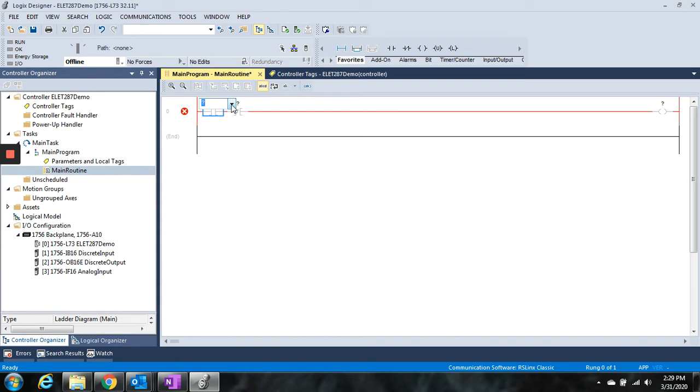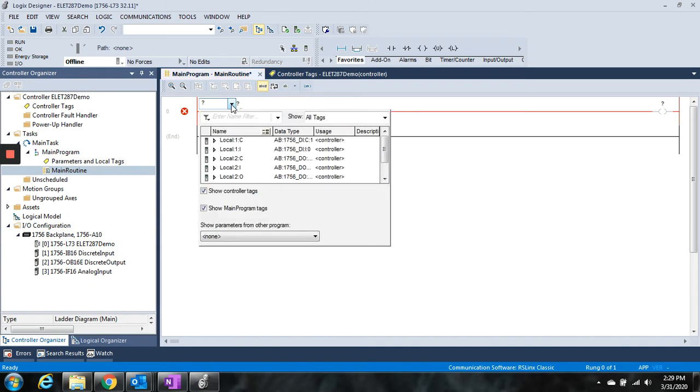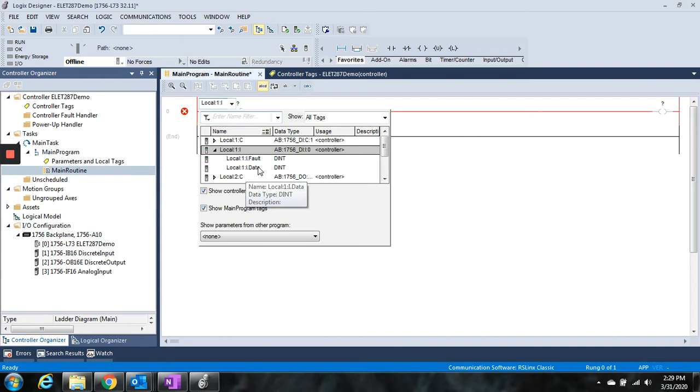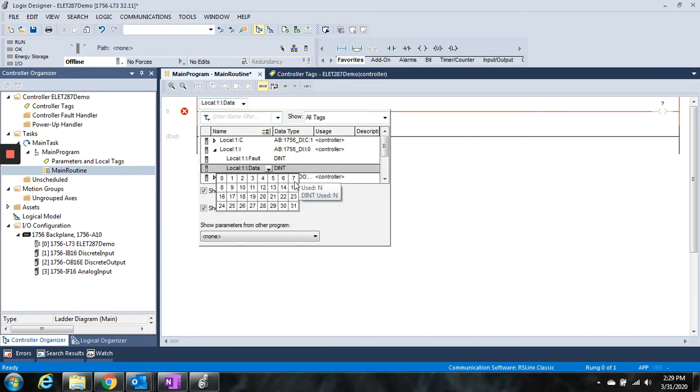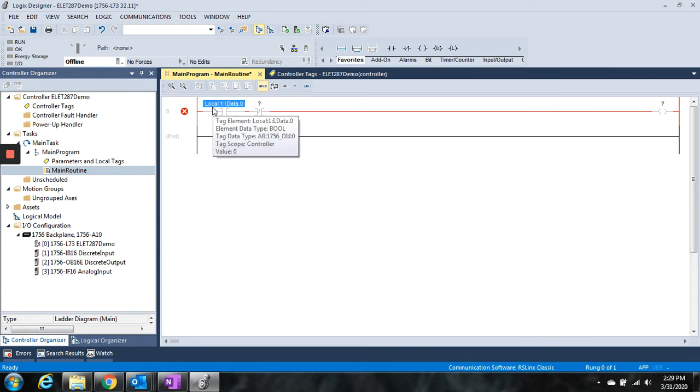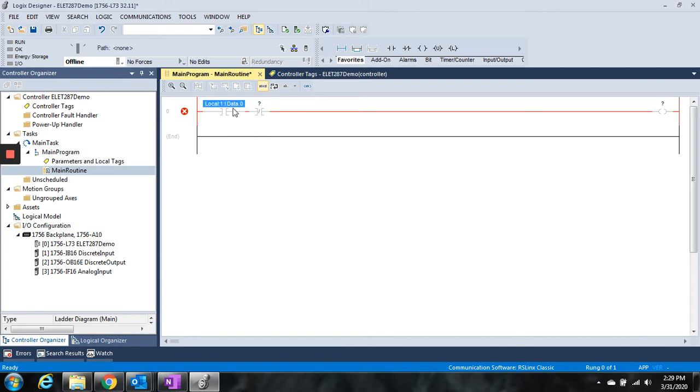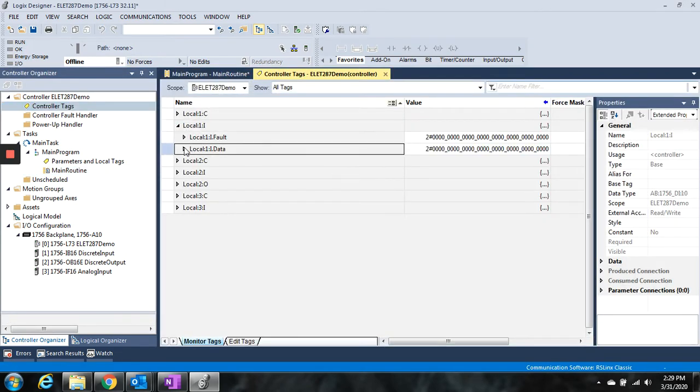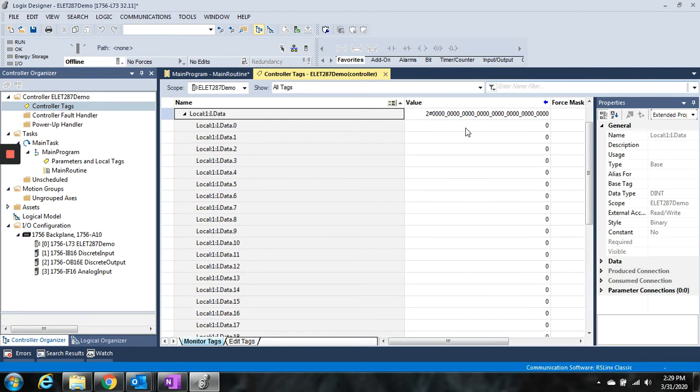So now I can search, and we're going to go to local 1:I, and we're going to go to local 1:I data, and we're going to choose 0. So that gives us the structure of local colon 1 colon I dot data dot 0. And that points back to this right here in the controller tag, which this points back directly to the input on the input card in the chassis.